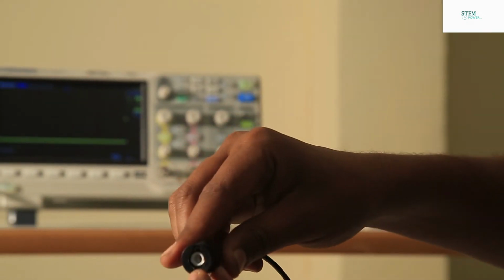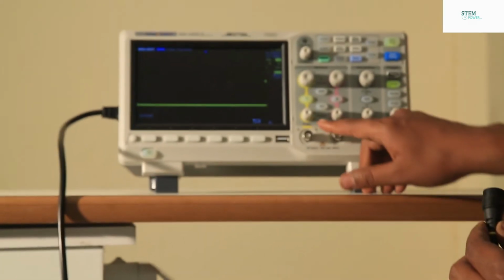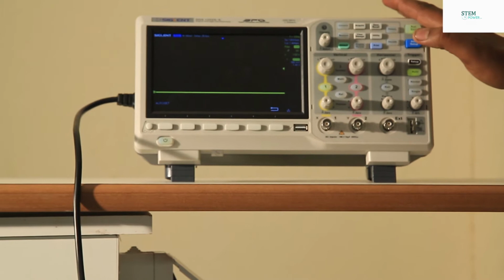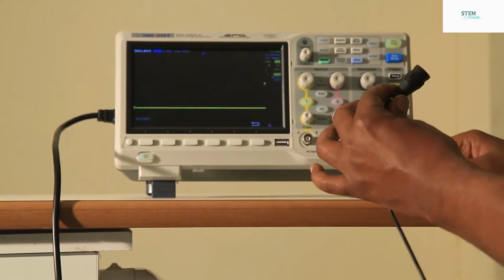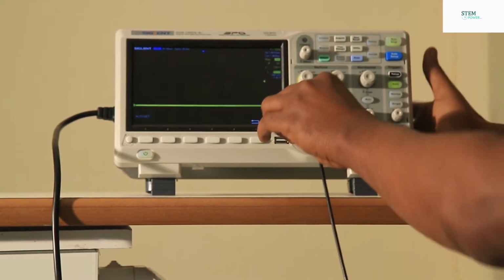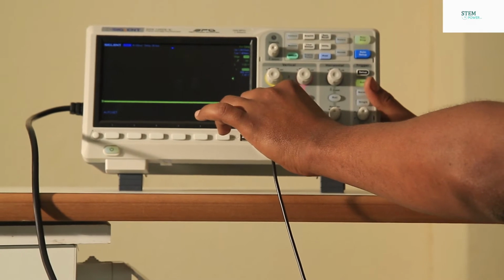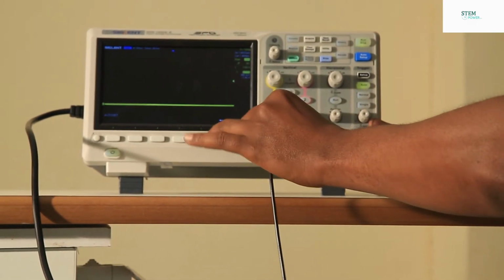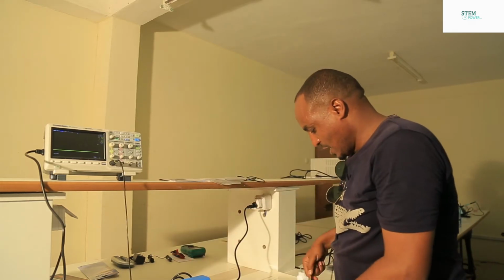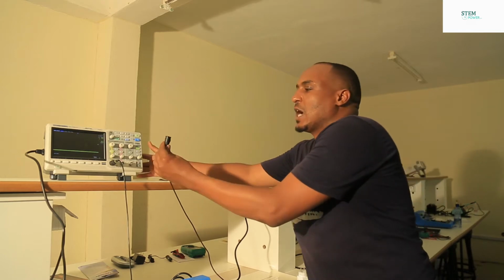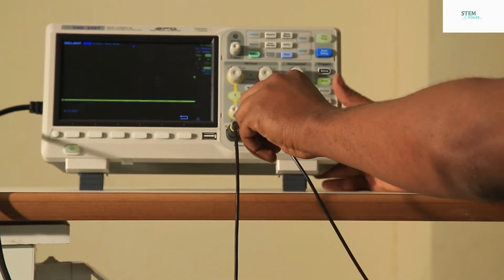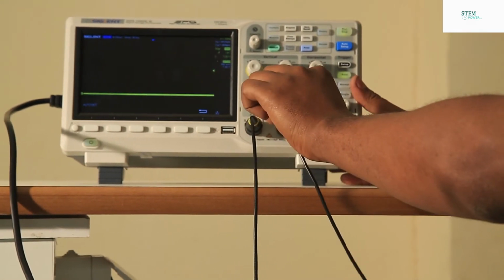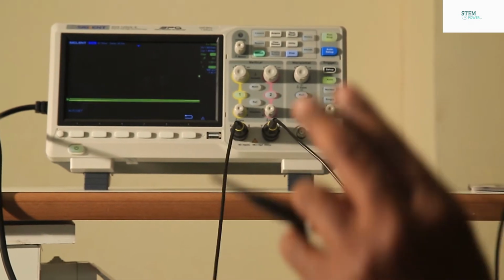This is the probe cable. It connects by aligning its groove, upper and lower, with the pin of the X channel—this instrument has two channels. Connect the probe this way, groove and pin, then turn to the right. If you pull it, nothing happens, so the connection is secure. With the same fashion, connect channel B, channel Y, turning it to the right. This is how you connect the probe.